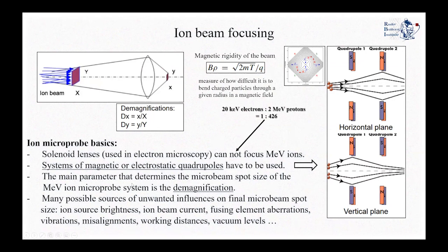While focusing, there can be many possible sources that influence the final microbeam spot size. Some of them include the ion beam current — one should start with a decent ion beam current to collimate and then focus it. The beam spot is also affected by aberrations of the focusing elements. Another important factor is vibrations induced by pumps or other components of the setup. Misalignments between the quadrupoles, the beam, and the slits are also important, as well as working distances and the vacuum level in the chamber and beam line.